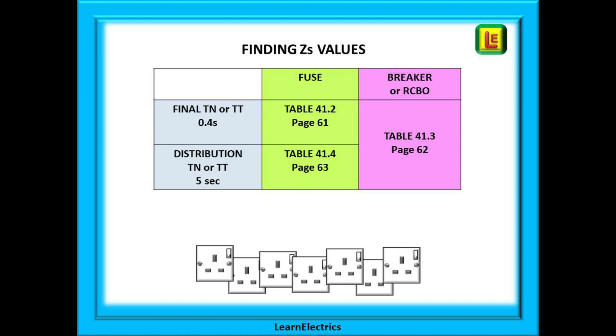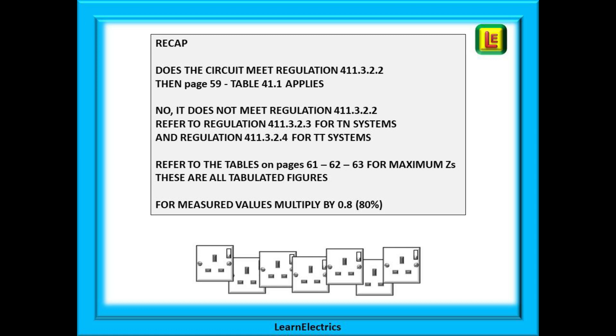This decision table should help you visualise the process. Decide if it is a final or distribution circuit on the left and choose a row. If it is a fuse, make your selection in the green column and find the ZS in the appropriate table shown. If it is a circuit breaker or RCBO, use table 41.3 to find the ZS.